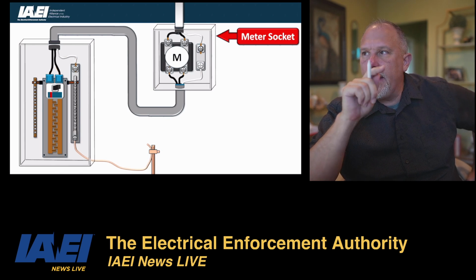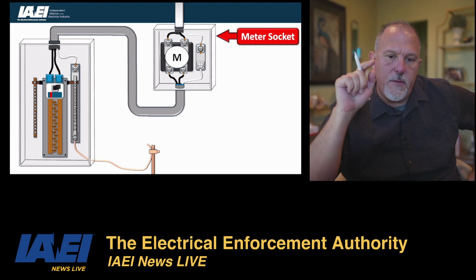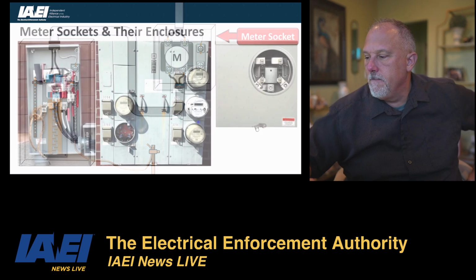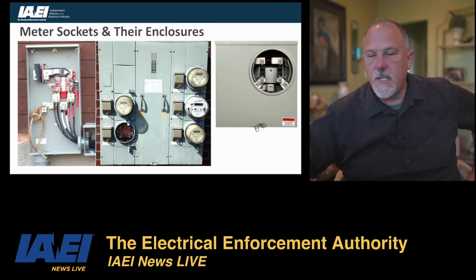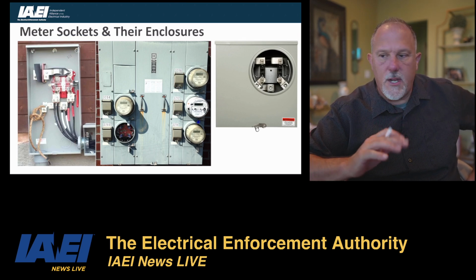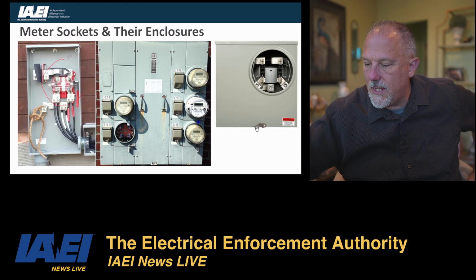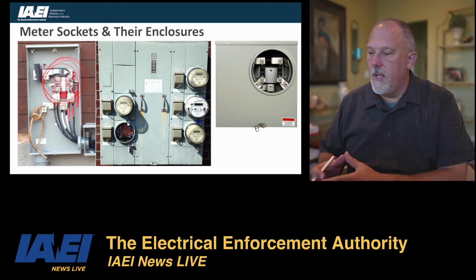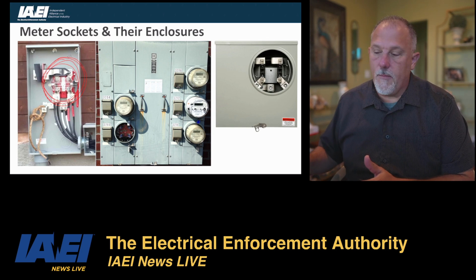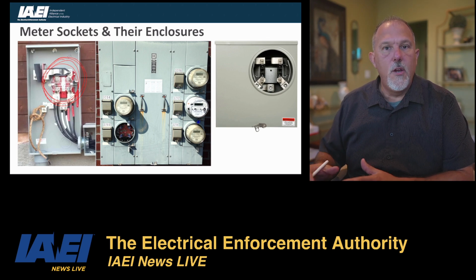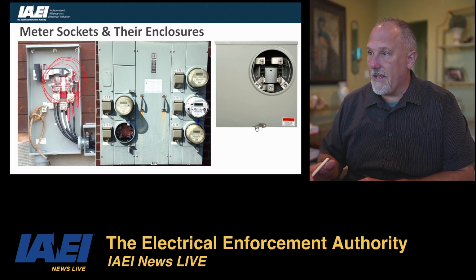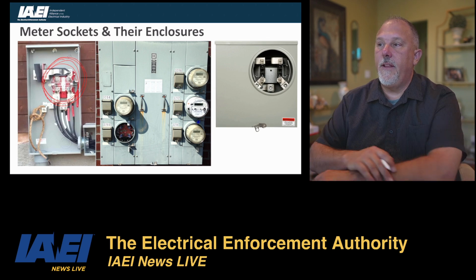You know that in 230.66, we talked about that already, that the meter sockets can come in. Now when I say meter socket, what I'm talking about is what's inside the enclosure. I'm not talking about metering equipment. I'm not talking about the enclosure. We're just talking the socket.